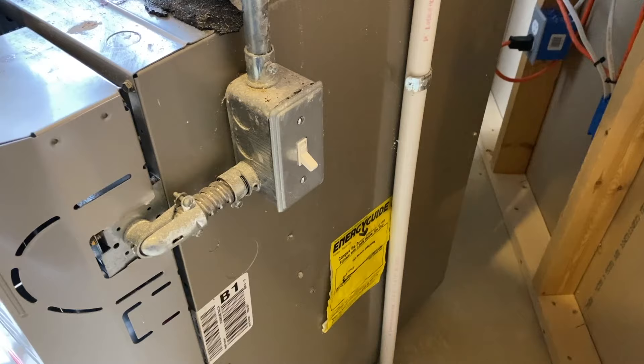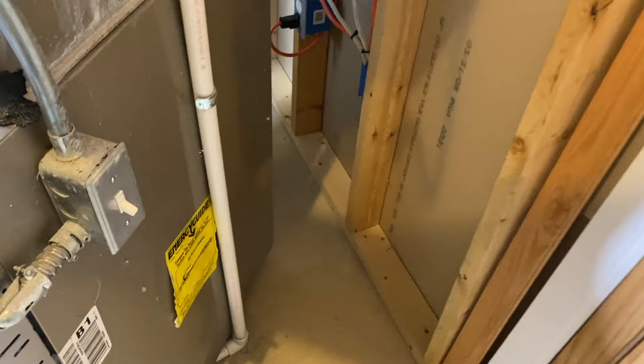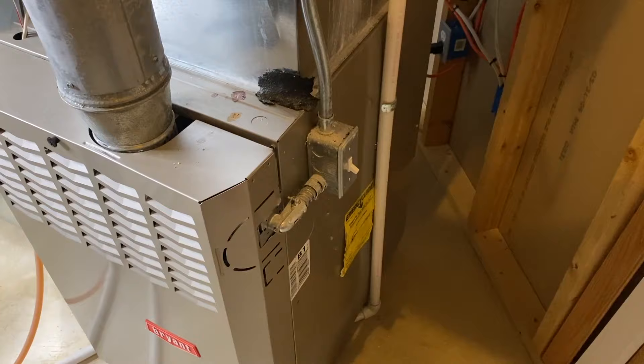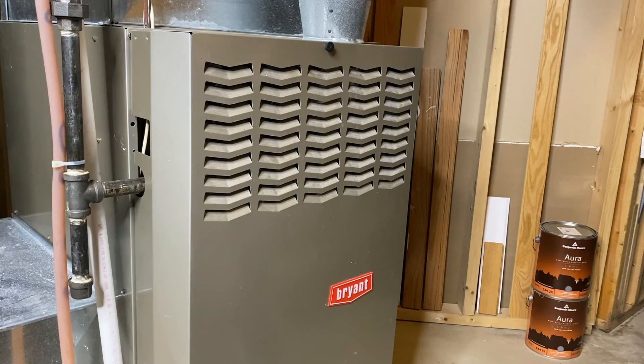Unfortunately, in uncommon circumstances, your switch may be accidentally turned off — caused by working around the furnace or moving stuff. I've got random baseboards, floorboards, hardwood, and paint in this area. In the event that I'm moving stuff around and accidentally turn that switch off while the furnace is running, or in the unlikely event that your children or even a pet accidentally turns that switch off, it will do the exact same thing as switching off the wall-mounted thermostat. It will turn the system down and be considered an interrupted cycle on the control board. This can also happen due to a recent power outage if the furnace was currently running when the switch was turned off.